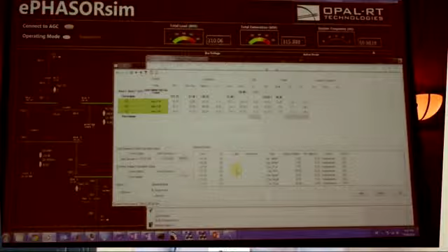So what this allows us to do when we actually deploy this for a customer is have an end-to-end simulation where they can go through a bunch of different scenarios, and you can tune and optimize the AGC. Everybody understands what the results are going to look like with the generations without stressing the generators up and down to go through the scenario. If you're delivering this as a solution and you're trying to get signed off on a factory acceptance test, you can go from this type of simulation out to the field, and the results should be the same. And the nice thing is we're going to model the generators in ETAP the same way, from the manufacturer data or from our libraries.